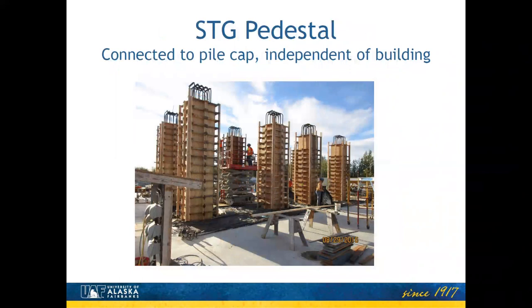Yeah, the steam turbine generator sits on a foundation that's independent from the rest of the building, and it's underlain by driven piles. That lets any vibrations from that machine get transmitted into the ground and not create harmonics in the rest of the building. So that was a complicated foundation to build.